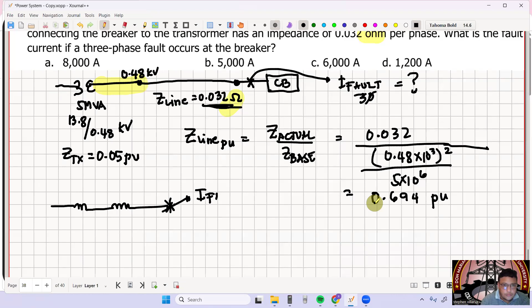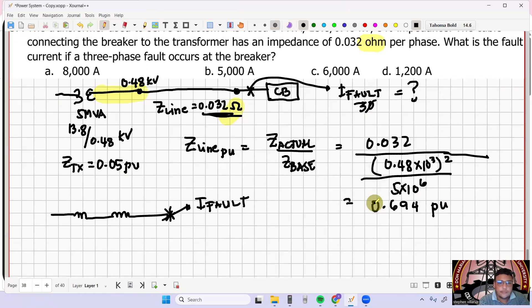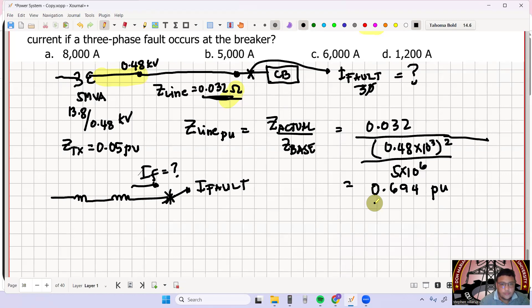So it looks like this, and here is the fault. What is the fault current here? How do we get it? I fault is equal to E per unit over Z total, which is 1 over 0.05 plus 0.694, multiplied by the base, so that it becomes amperes. What is our base? Base S is 5 MVA, and the base voltage, since it is on the secondary, is 0.48 kilovolts or 480 volts.